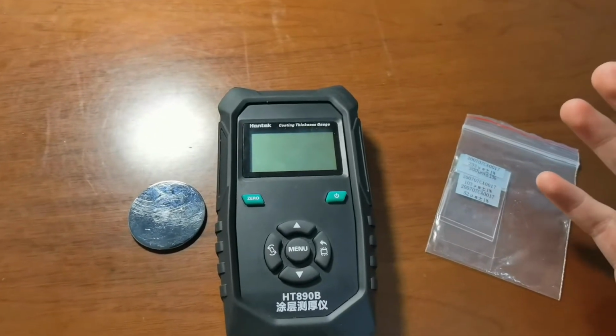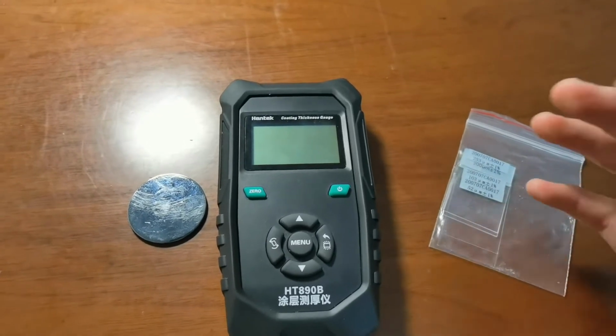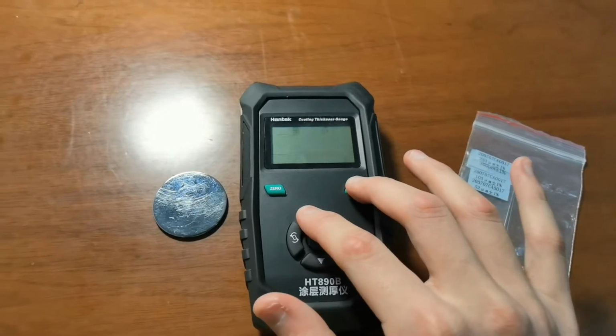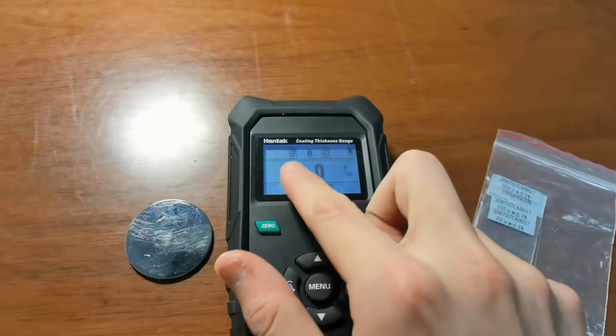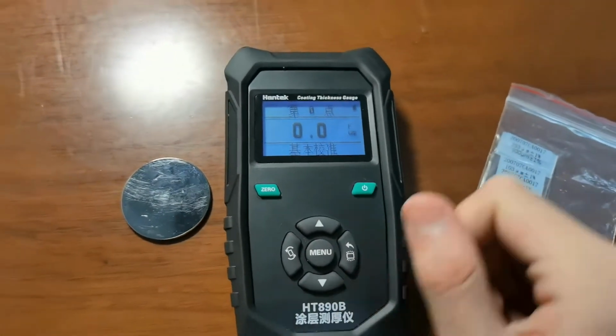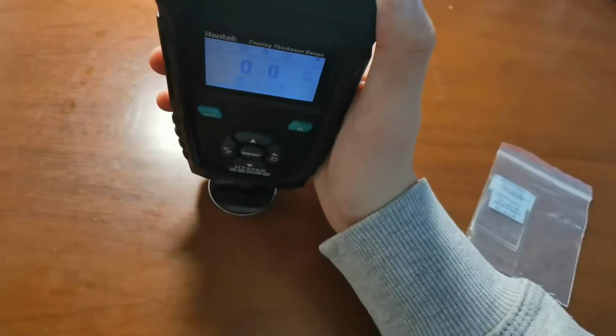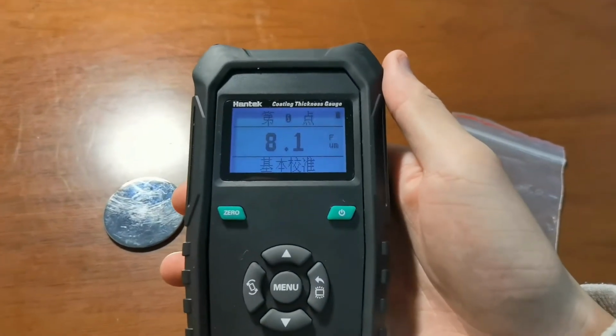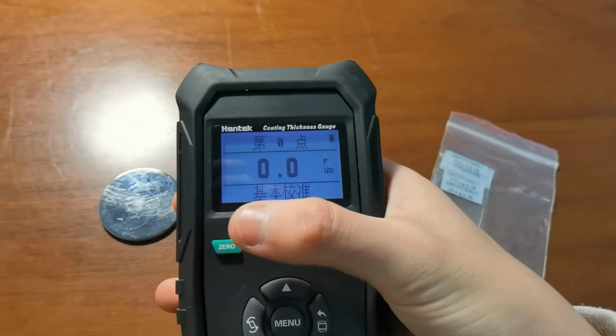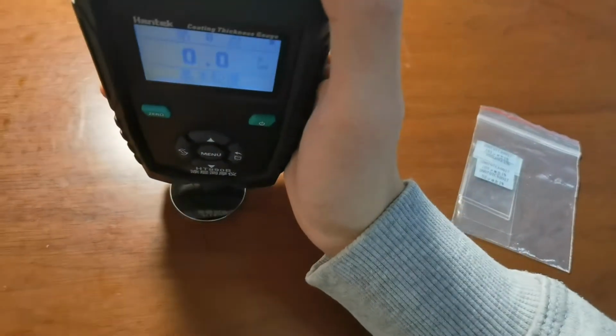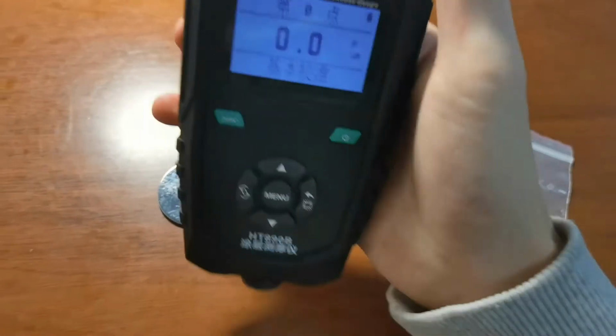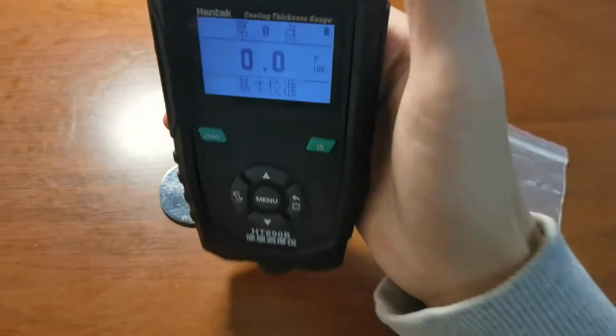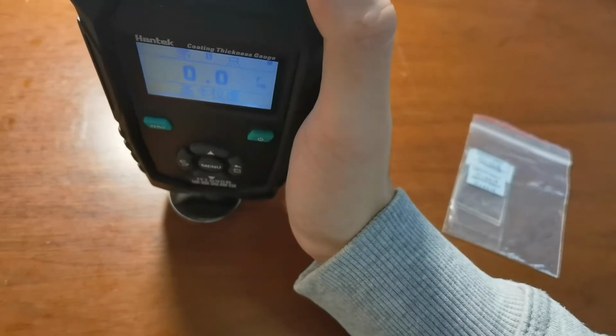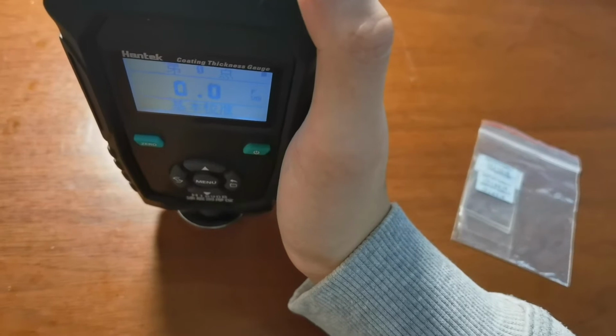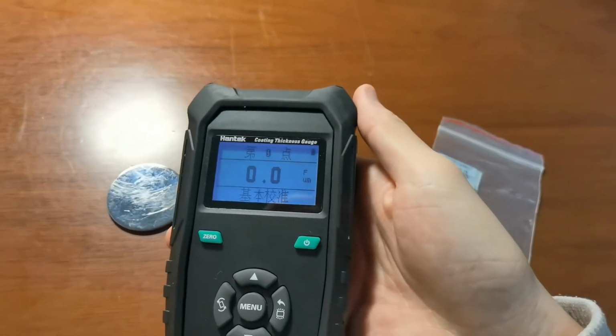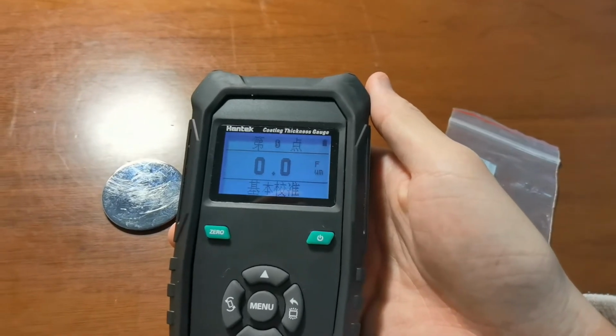Hold down the up key and the power on key at the same time until the calibration interface appears. Okay, now we are going to carry out 0.0 calibration. Okay, press the probe onto the ferrous substrate. After the gauge displays a value, press 0 key. And then repeat this step 3 or 4 times. Okay, then the 0.0 calibration has been done.